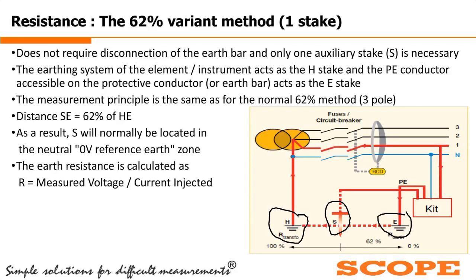So by using these two existing earthing connections as two stakes, we can perform the measurement with the help of one auxiliary stake. So in this method, only one point you have to keep in mind, that the distance between S and E is 62% of the distance between H and E. So that's why it is called a 62% variant method.